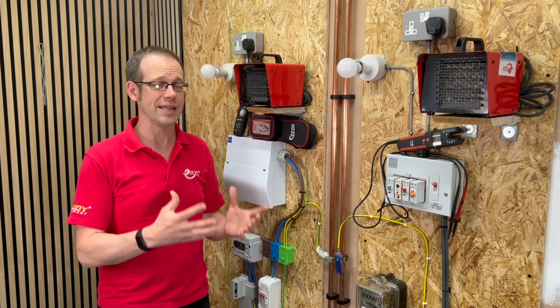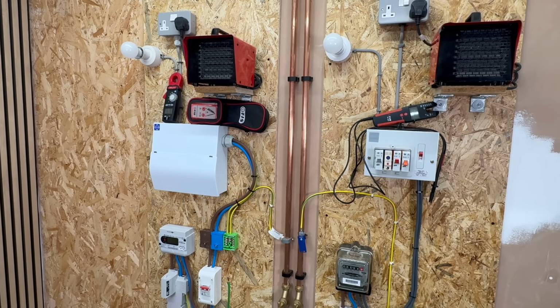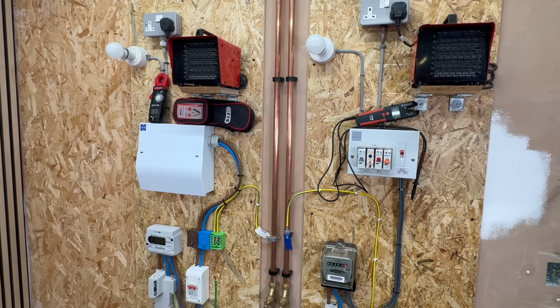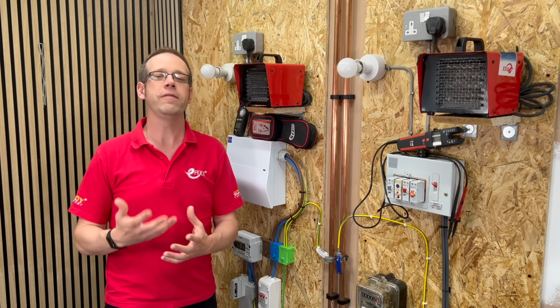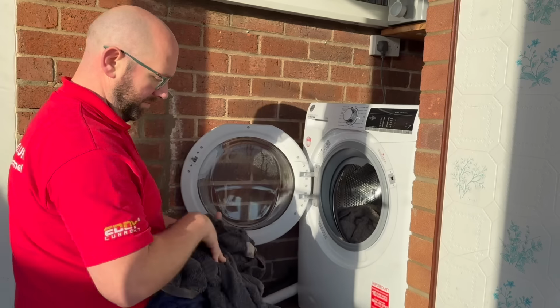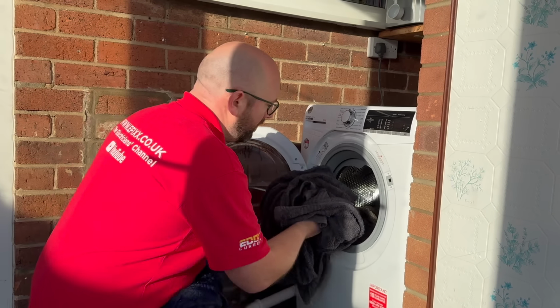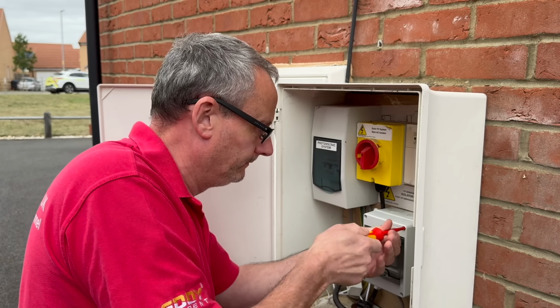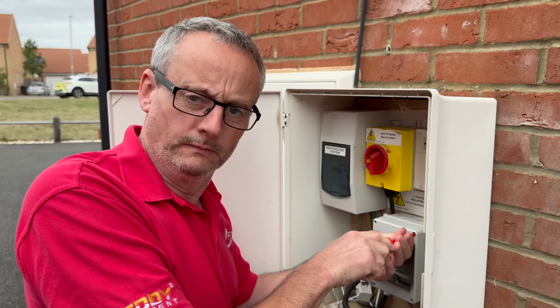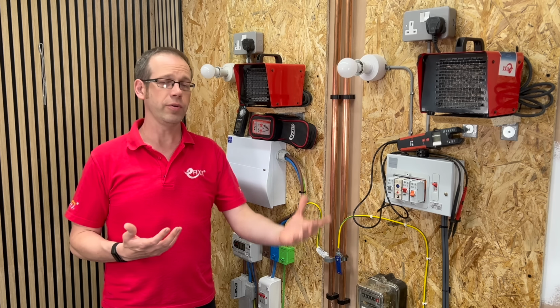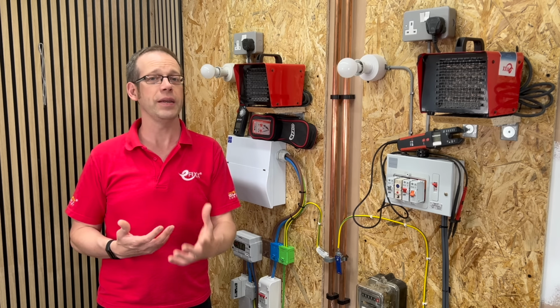There are a lot of different scenarios and situations where this could occur, and we've just looked at 2 examples. It's impossible to outline all the variations in a concise video, but however it's occurring, is it that big a deal? Well, there are a couple of dangers that this situation represents. One is a problem for the homeowner that will vary in degrees of seriousness. The other is hazardous to anyone doing electrical work. The problem for the homeowner is that the current flowing through the earthing conductors in their property might not be the end of the story.